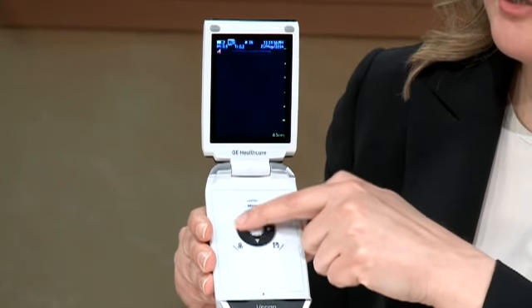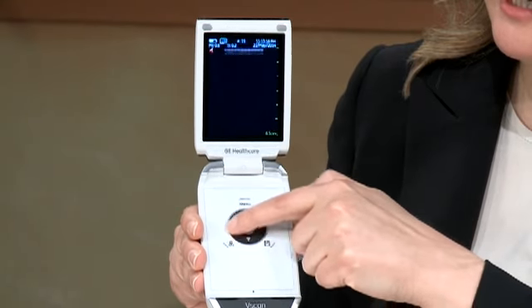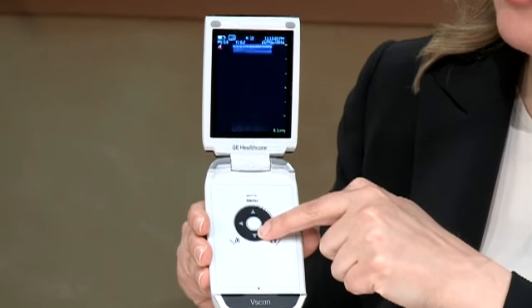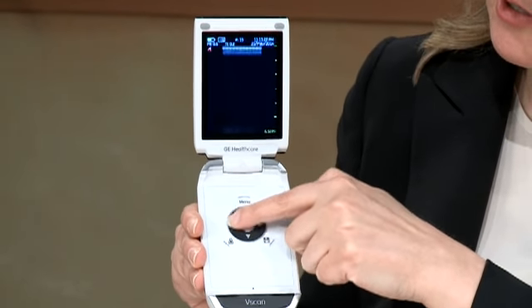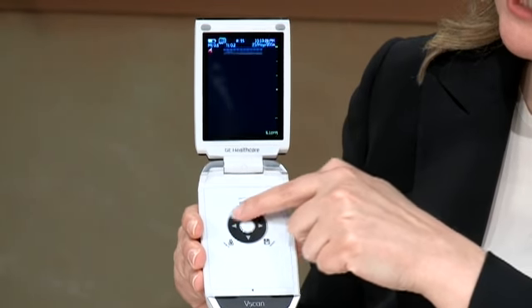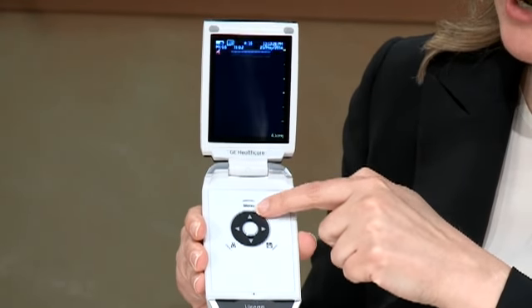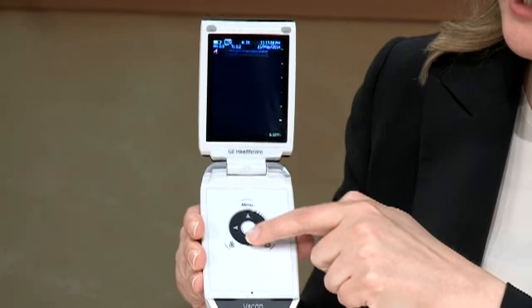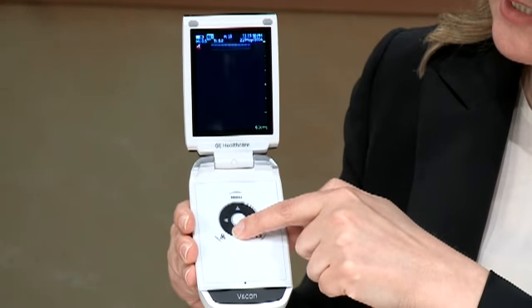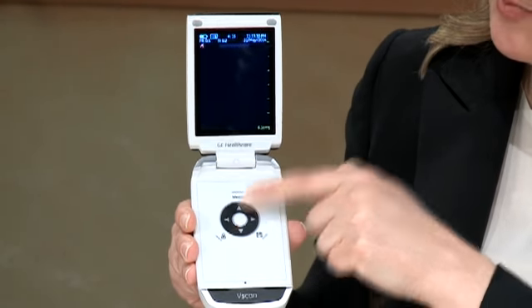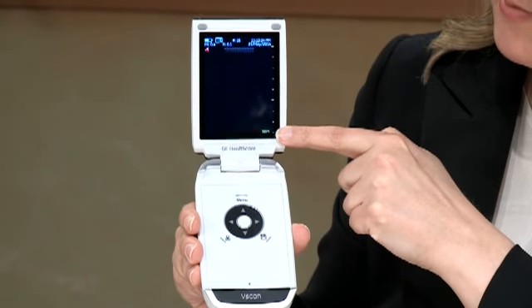Let's take a look at the shallow transducer's general user interface. The probe will automatically activate to black and white scanning. The black wheel in a clockwise motion will serve as the gain increase for this transducer. Counterclockwise will decrease the gain. The up and down arrows support the depth function. Here I'll press the down arrow and you'll see a response displayed on the monitor.